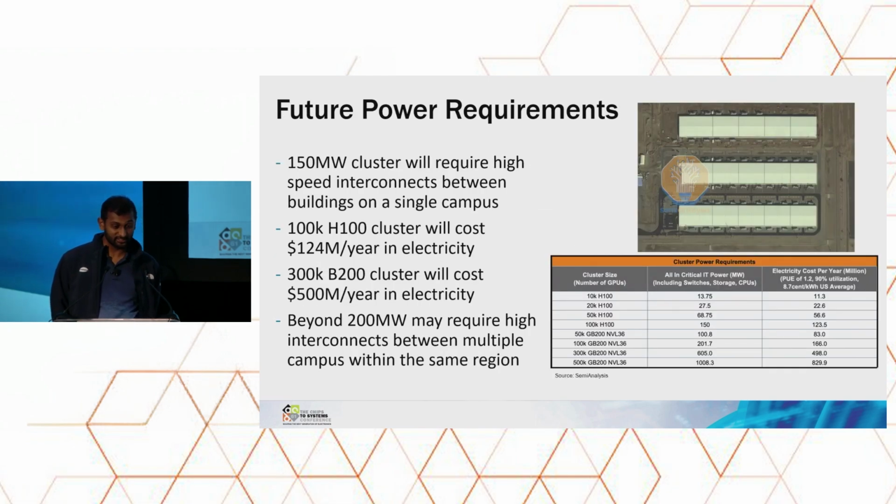So today this is a satellite image of Arizona for Microsoft. This is 3 data centers that they've tied together to train a model. The third data center is actually in construction, but it's a few months old picture. It's actually complete now. Each of those buildings is 48 megawatts, roughly 150 megawatts total for all 3. And they have to interconnect multiple buildings. It's not the same as just using optics to connect servers in a rack or between racks. No, we're going between buildings. These are miles of interconnect, hundreds of miles in aggregate fiber just for one training cluster.